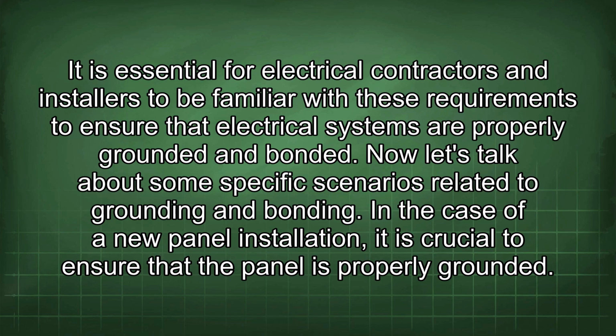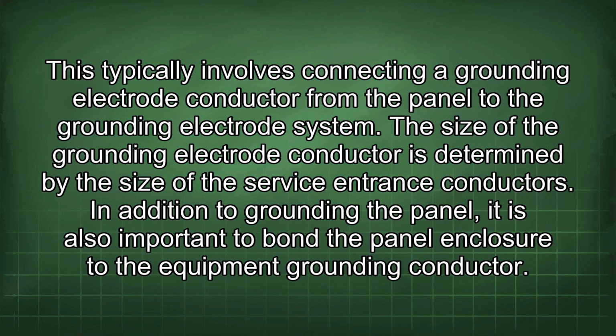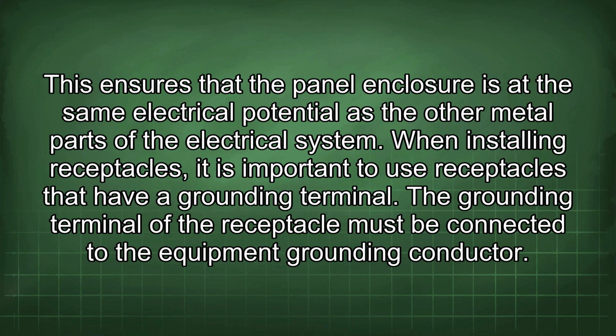In the case of a new panel installation, it is crucial to ensure that the panel is properly grounded. This typically involves connecting a grounding electrode conductor from the panel to the grounding electrode system. The size of the grounding electrode conductor is determined by the size of the service entrance conductors. In addition to grounding the panel, it is also important to bond the panel enclosure to the equipment grounding conductor.